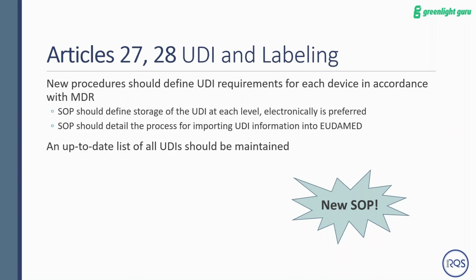So UDI and labeling. UDI requirements are detailed in the standard as well. Big change, obviously, no UDI requirements previously. Typical path, if you've done it in the US, is to get your UDI code or GUDID code from whatever, maybe GS1 is a common one, and you then have to have that code embedded in the barcode or QR code for your device, and make sure the information tied to your device is current on all levels of packaging and labeling. And part of the requirements for MDR is that you have to define storage of UDI at each level. Electronically is preferred, and that's straight from the standard. So you want to have an electronic method of tracking what UDIs you've issued, as well as updates to UDIs and where those devices are.